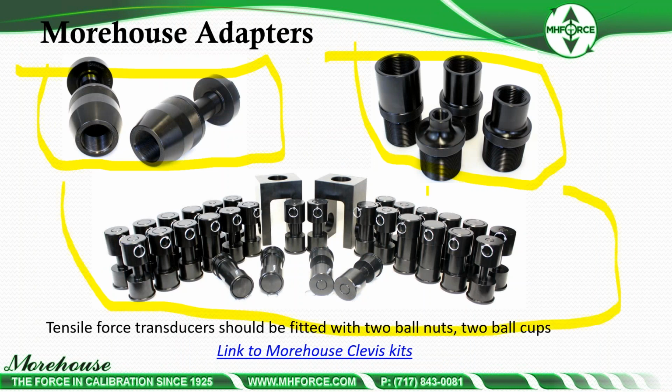And then if you have dynamometers, ED2000s, other ones, Tractel, Dillon, all those, there's pin size requirements. Not calibrating with the proper pin size can produce errors 17 to 20 times the actual tolerance of the device. So all these are mated with the right pins, the right shoulders, the right strength. They have at least a 2-to-1 safety factor on all of them, and there's a chart that if you want to calibrate a Dillon ED 25K, ED2000 25K, it'll tell you exactly which pin size you need and what part number to go pull and fix everything up.